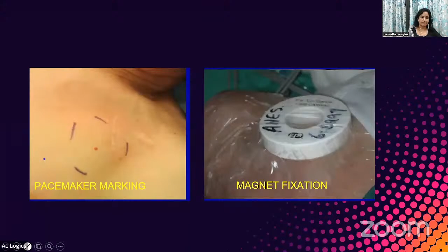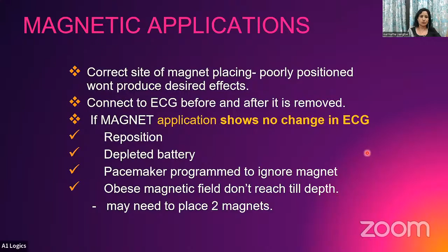So for example, if you are seeing no changes in the ECG, you can think of one thing: your position is not correct, or there may be a depleted battery. Third, the pacemaker is programmed to ignore the magnet. Fourth, the patient is very obese so that the depth doesn't reach the pulse generator. So in an obese patient, you may need to place 2 magnets.